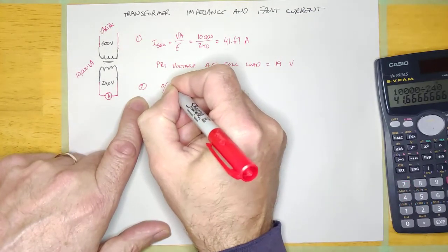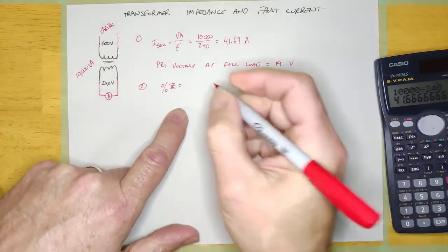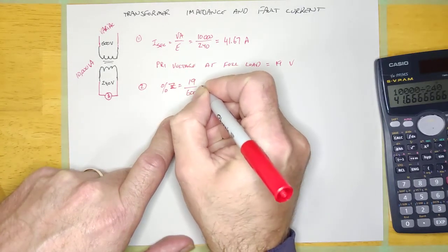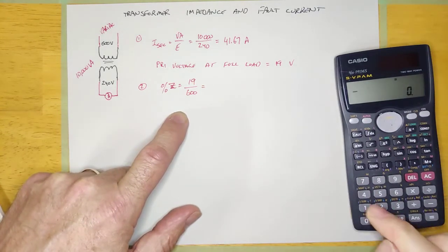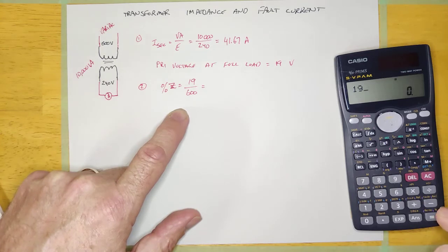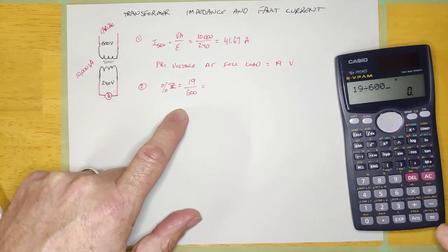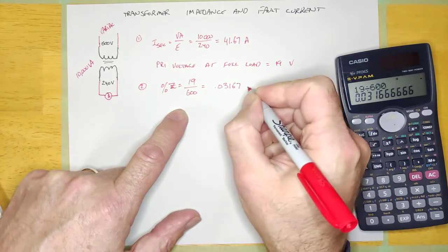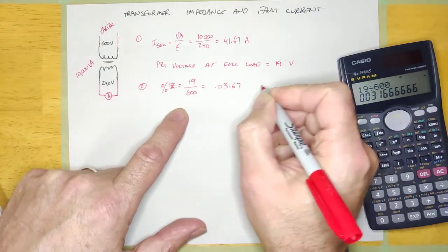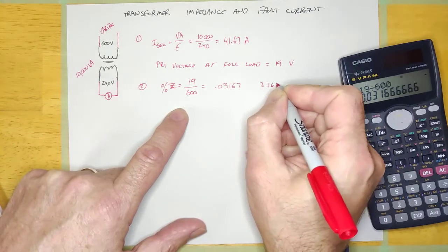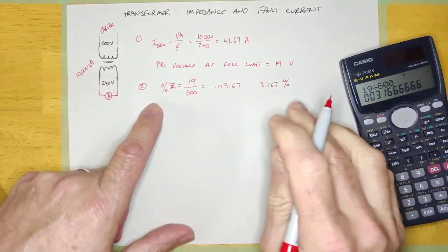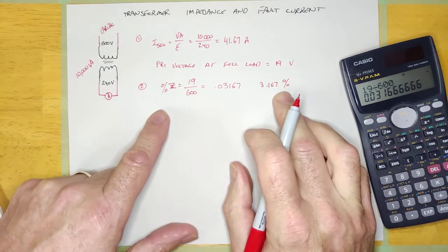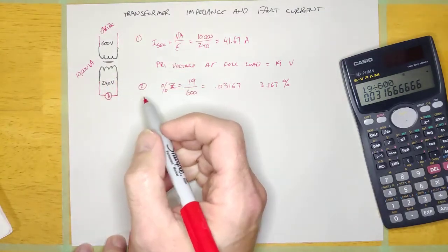After you've done that, you now have enough information to calculate the transformer's percent impedance. Because the percent impedance, percent Z, if you look at your notes, is the measured voltage over the rated voltage of the primary. So it would be the 19 volts that it took to get this thing to run at full current under short circuit conditions divided by the rated primary voltage. And it comes to 0.03167, and we would multiply that by 100, and we would get 3.167%. So the percent impedance for this particular transformer is 3.167%.